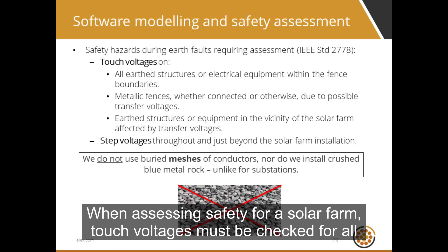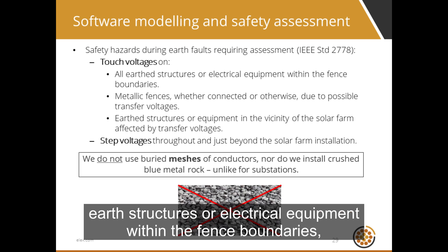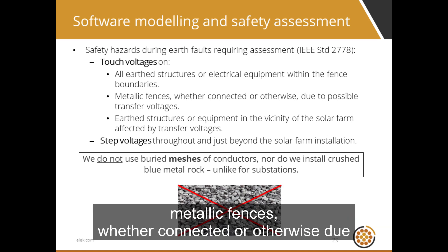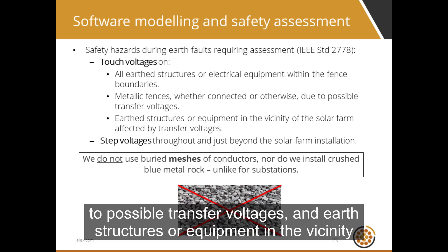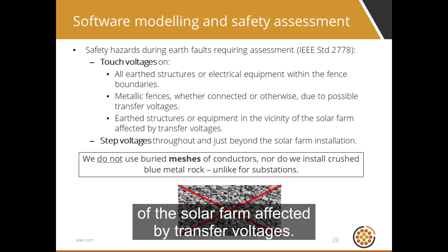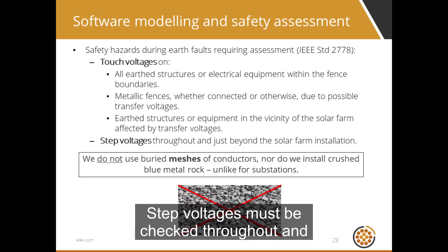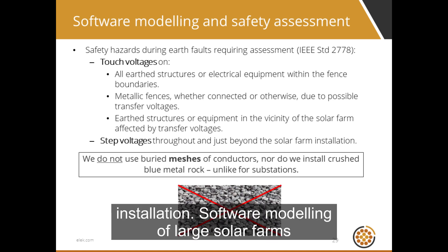When assessing safety for a solar farm, touch voltages must be checked for all earth structures or electrical equipment within the fence boundaries, metallic fences whether connected or otherwise due to possible transfer voltages, and earth structures or equipment in the vicinity of the solar farm affected by transfer voltages. Step voltages must be checked throughout and just beyond the solar farm installation.